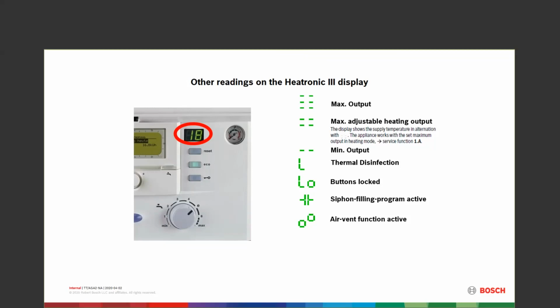It's designed to get rid of the air that might be in the system or in the boiler side of this. So air that's in the domestic water side, when we're first turning things on in the plate heat exchanger, air that's in the valving, air that's in the boiler loop itself. That vent function is 4 minutes. Can be taken out, but generally we leave that right in and leave it right there as it should be.